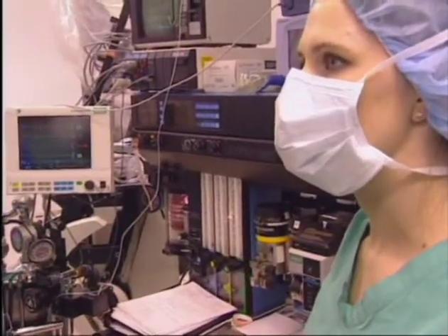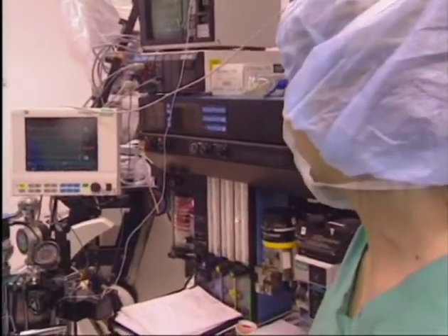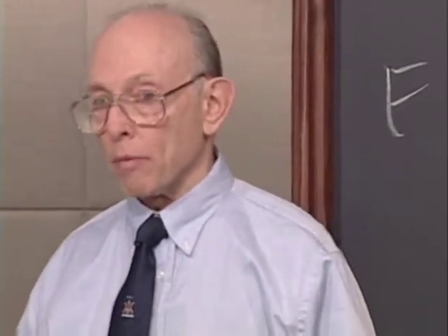The minimum flow is 1 liter per minute. So with sevoflurane we shouldn't go below that. Right. 1 liter per minute flow rate. Right. That covers what we need to do in terms of keeping safe and avoiding any problems with compound A.